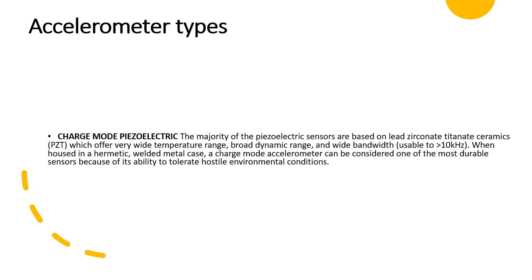One type of AC coupled accelerometer is the charge mode piezoelectric accelerometer. The majority of piezoelectric sensors are based on lead zirconate titanate ceramics, which offer a very wide range of temperatures, broad dynamic ranges, and wide bandwidths up to more than 10 kilohertz. When housed in a hermetic, welded metal case, charge mode accelerometers can be considered the most durable sensors because of their ability to tolerate hostile environmental conditions.